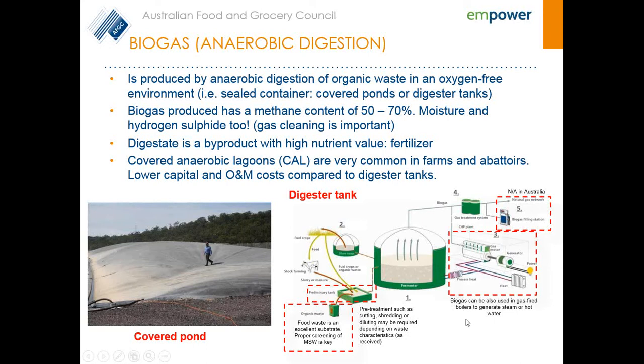A lagoon is basically a hole in the ground with some lining. It receives the wastewater stream from your process, sits there for a number of days, you just cover it, and the gas produced is captured by a blower and goes to a flare or can be supplied directly to the process. A digester tank is much more complex and has a number of other components associated with it.